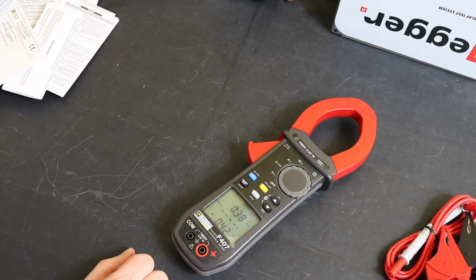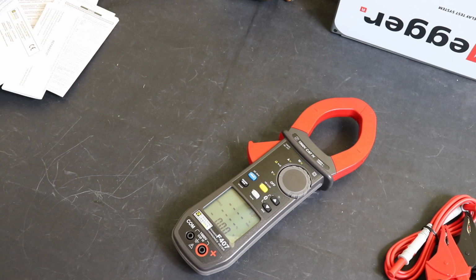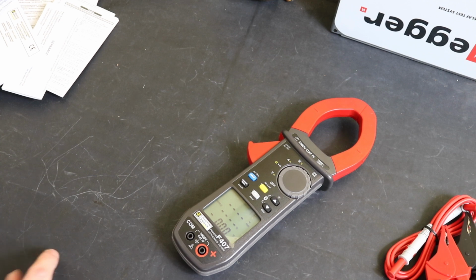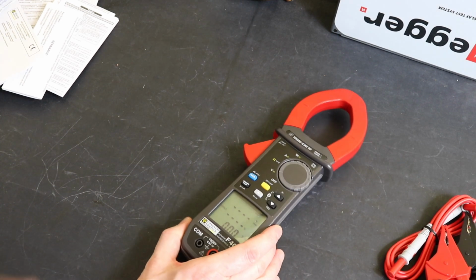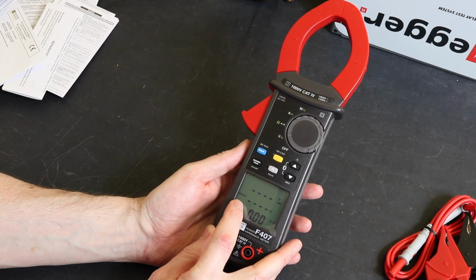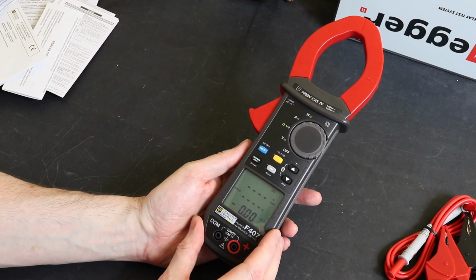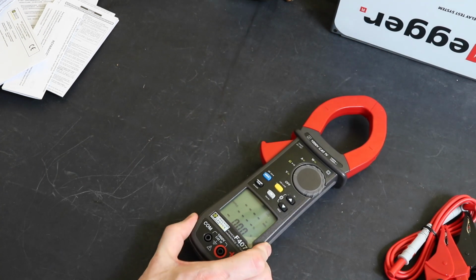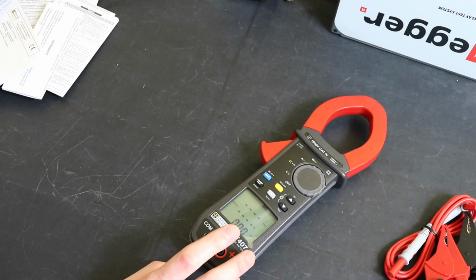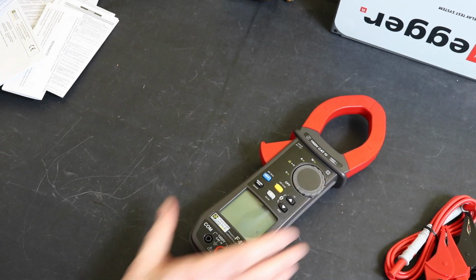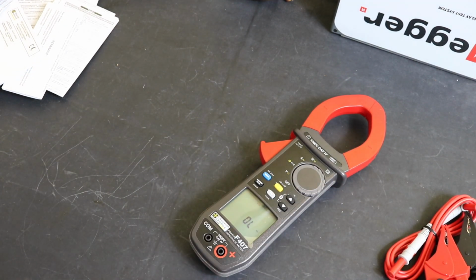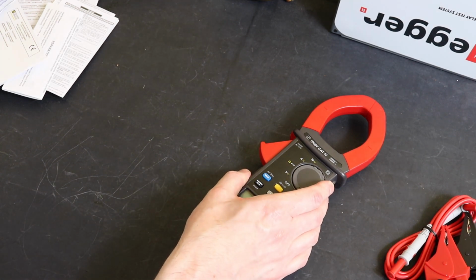Fairly easy set of ranges. We've got our volts, AC and DC on there. Can read from 200 millivolts way up to 1000 volts, both AC and DC, both at 1% plus 3 digits. You do have a ripple on there as well, interestingly enough. Don't often see that on an instrument, not as a main function anyway. So it does measure the ripple automatically within that. And then we move on to our ohms and continuity. Ohms, we're up to 100 kilohms for that one there. I'm not sure what the continuity level is, we'll look at that when we start testing.